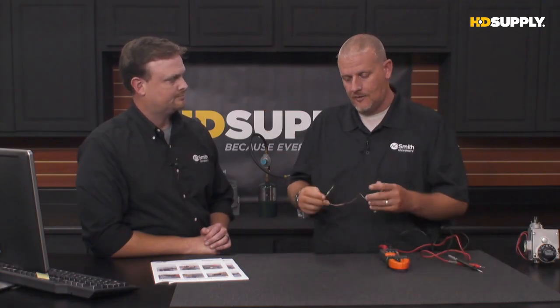We used to get out of the truck in the old days with one of these in your back pocket because you knew that's what it was. Eventually every 10 years you're going to run around and replace thermocouples in the heaters. So you just hop out of the truck with one of these in your pocket because you pretty much knew that's what the case was.